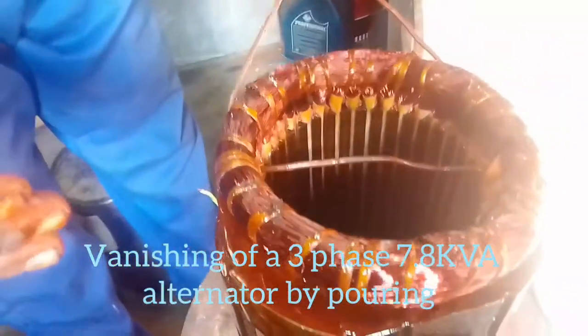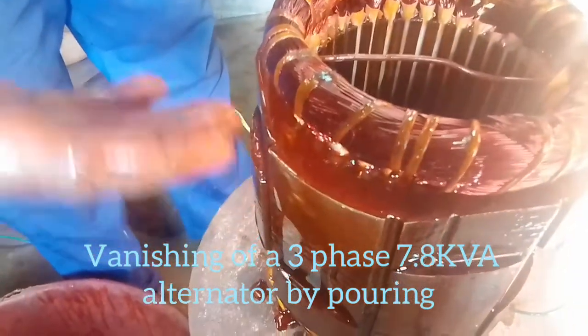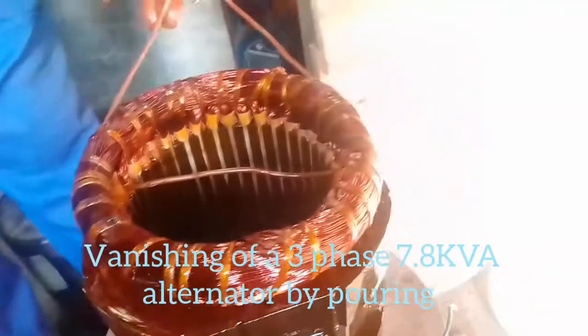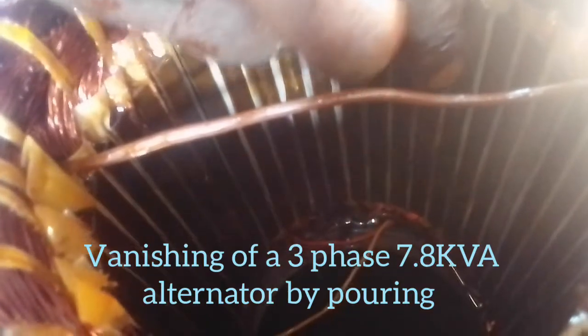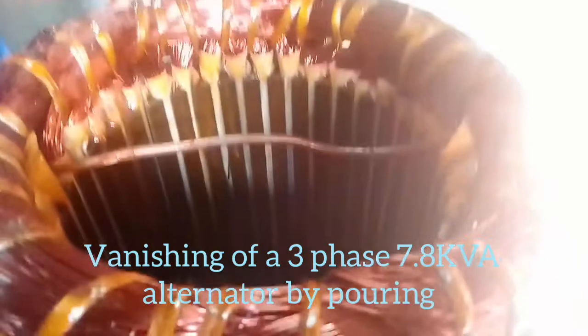Now keep the stator hanging. After coagulation — coagulation means when it gets clotted, since the varnish initially comes in liquid form — when it gets clotted, you use something like a smooth blade and gently scrape off the excess varnish on the stator core to make sure the air gap is very free, smooth, and clean.